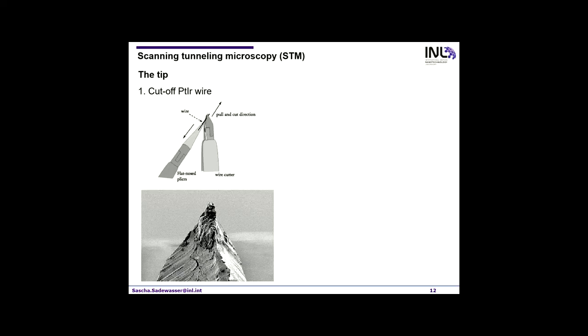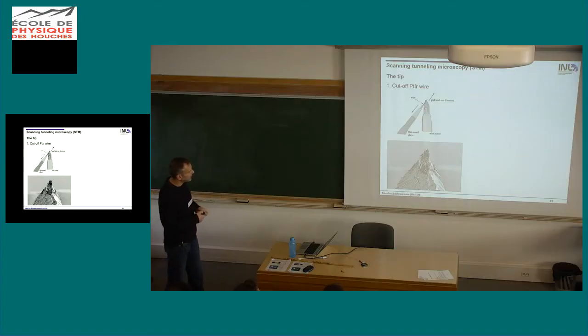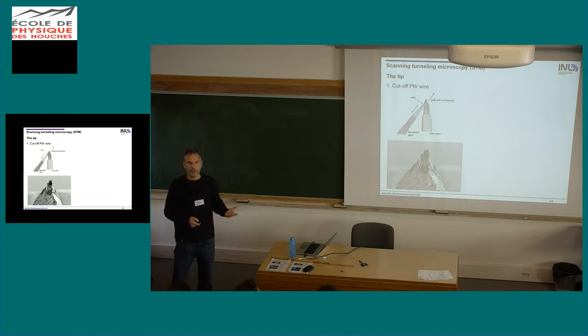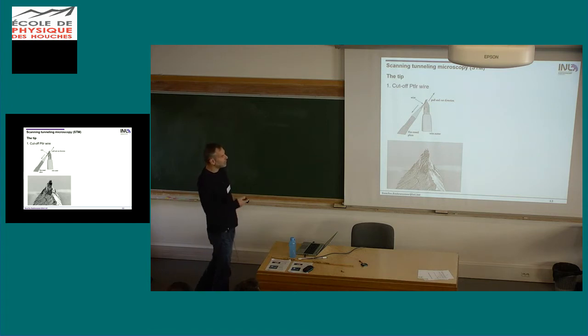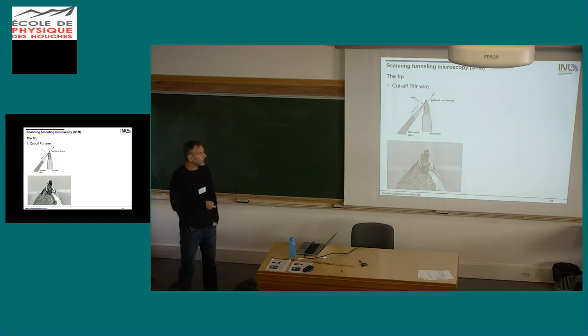So for the tip, initially people used just a wire cutter and a platinum iridium wire, platinum iridium because it doesn't oxidize easily. So you can do this outside or in air and then go to your vacuum system. Normally scanning tunneling microscopy is done in vacuum, ultra-high vacuum. But your tip doesn't look really nicely.